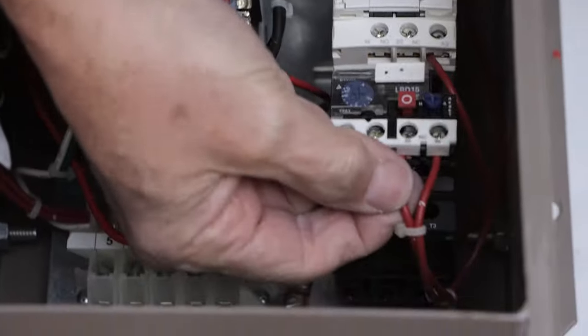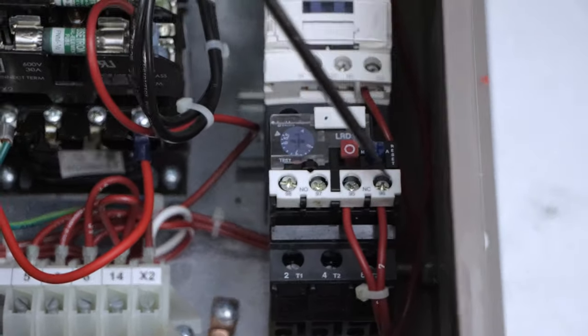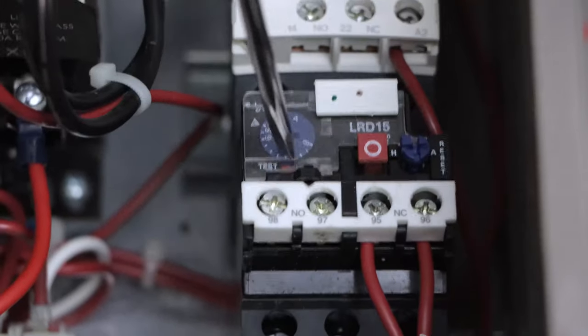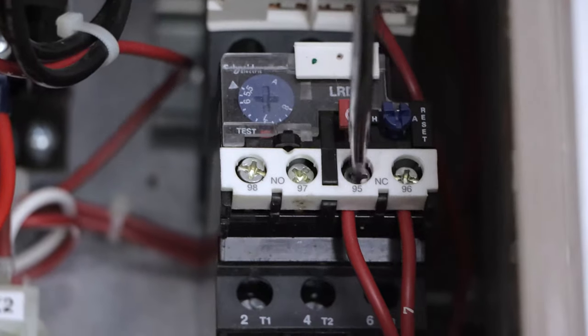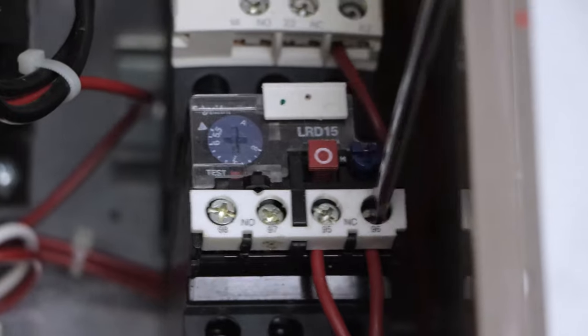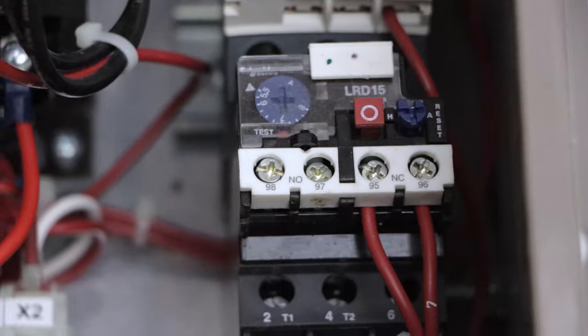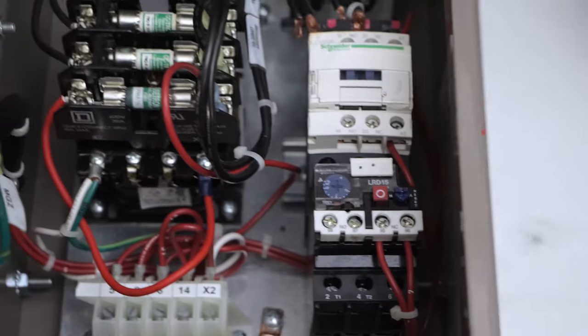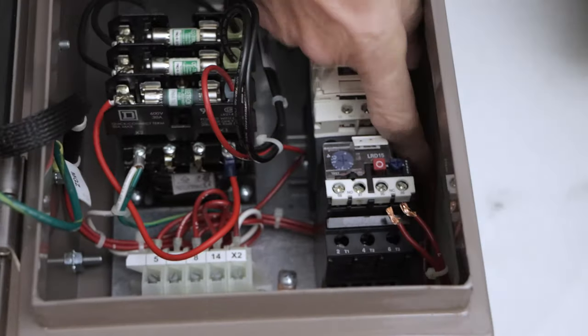Okay, now we don't have any load conductors here. We've got a couple of control wires here, which we'll get into eventually. Now this is a normally open overload, that's normally closed overload, and we'll get into that probably in a little bit later lesson why these are so handy. For the most part, these normally closed contacts are the same normally closed heaters that we've always seen to the right side of the motor coil. We take these out, this is going to be two and three, which is going to be our auxiliaries, going to the coil.